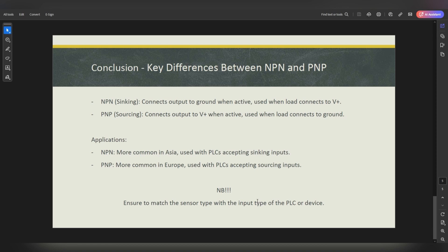In terms of applications: NPN sensors are mostly and commonly used in Asia when the PLC accepts sinking inputs. PNP sensors are mostly used in South Africa and Europe, when the PLC accepts sourcing inputs. One important thing to ensure before connecting a sensor to a PLC is that the sensor type and the PLC input type match each other, so you don't connect 24 volts to zero or vice versa. Also note that some sensors have short circuit, reverse polarity, or overload protection — always choose the best sensor for the job.